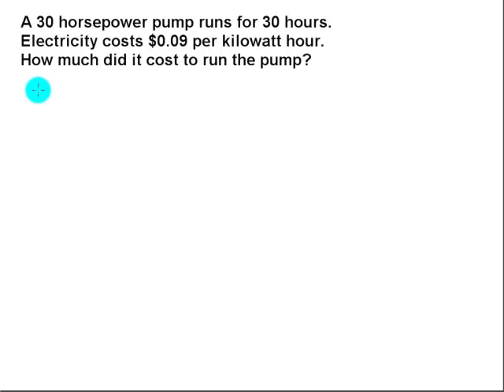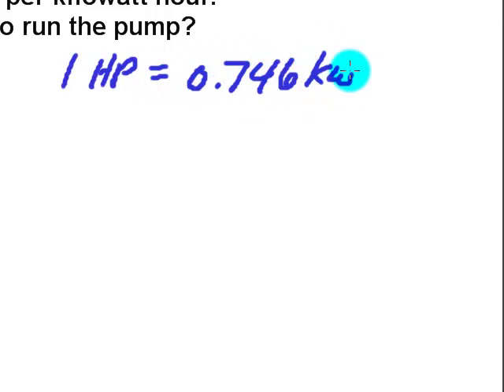So what we're trying to do is we're trying to take 30 horsepower and somehow magically turn that into dollars. And it's actually not too difficult if you know the secret. And the secret is that one horsepower is equivalent to .746 kilowatts.